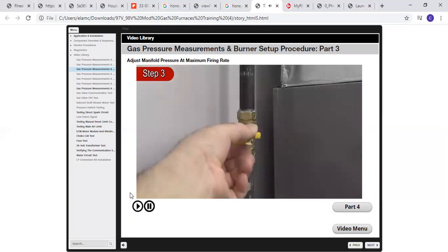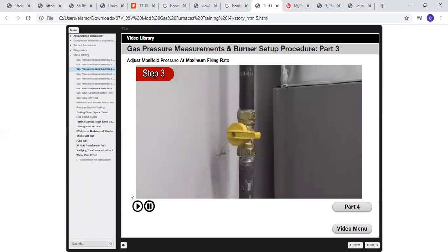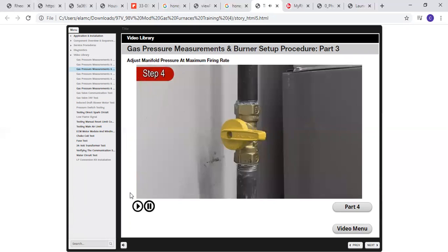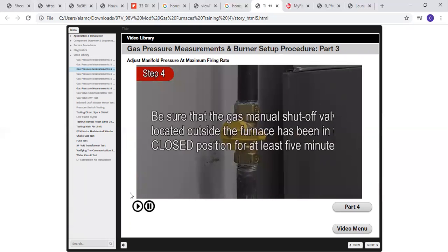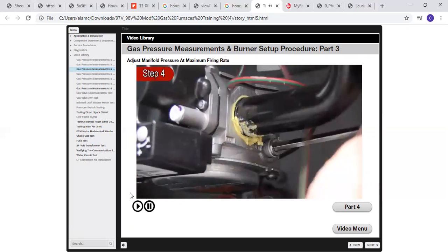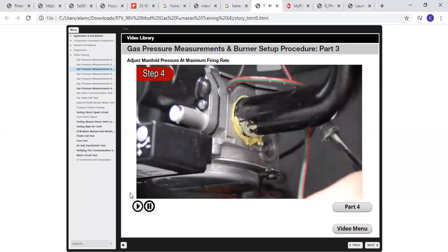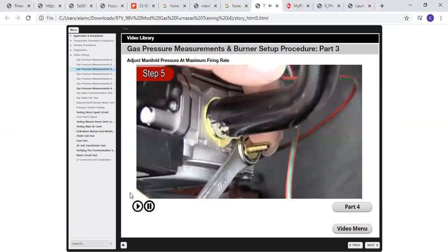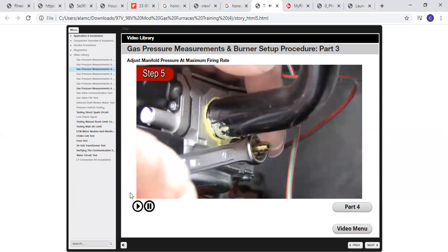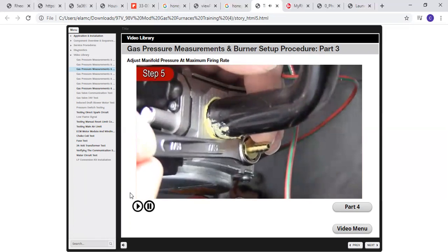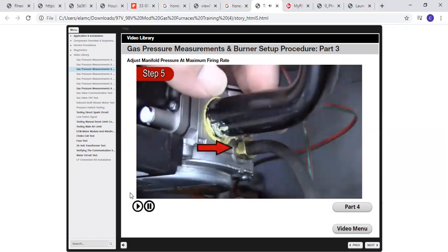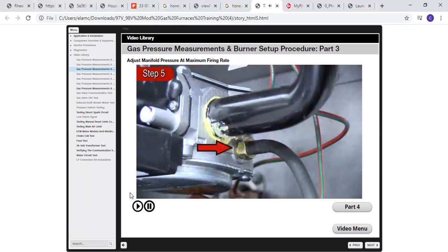Turn the gas manual shutoff valve located outside the furnace to the closed position. Step 4. Important. Be sure that the gas manual shutoff valve located outside the furnace has been in the closed position for at least 5 minutes. Remove the outlet manifold pressure tap plug in the gas valve. Step 5. Install the field supply pressure tap to the outlet manifold tap. Connect the positive pressure hose from a manometer to the pressure tap.